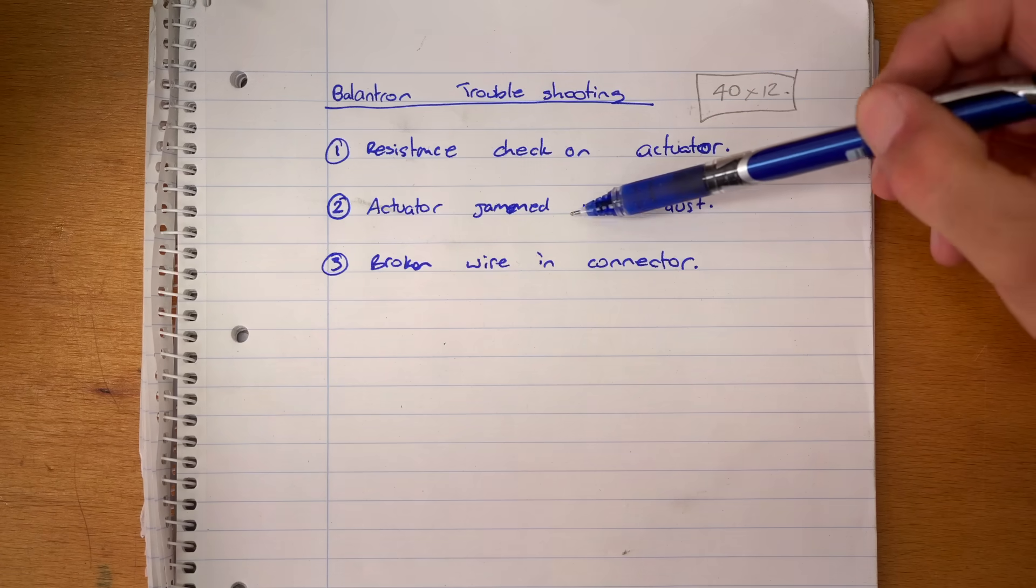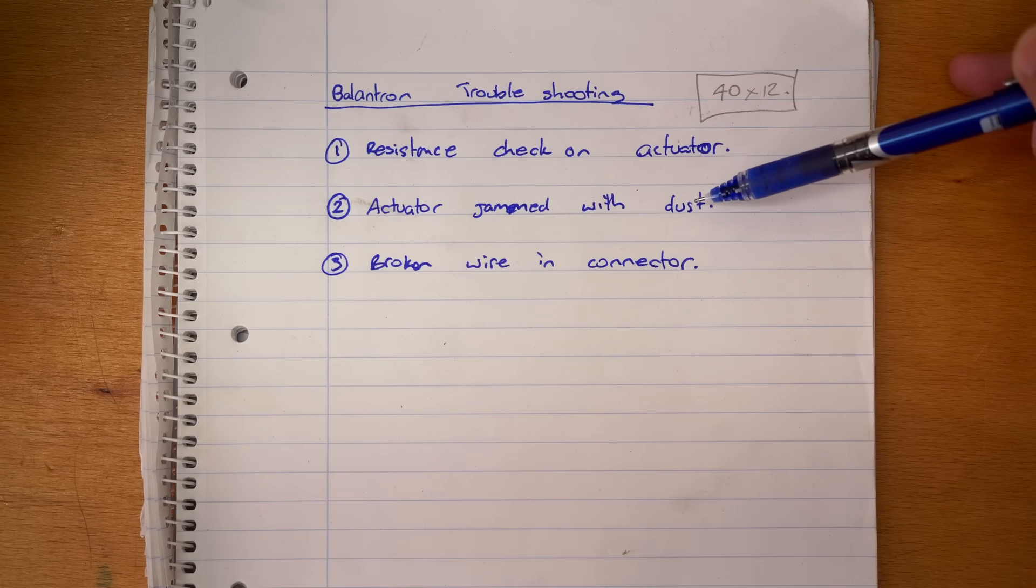Second thing it could be is that it's just mechanically jammed up, gummed up with maybe grease or dust or something. The third thing to look at would be whether there's a broken wire either in this connector or out on the other side in the controller.